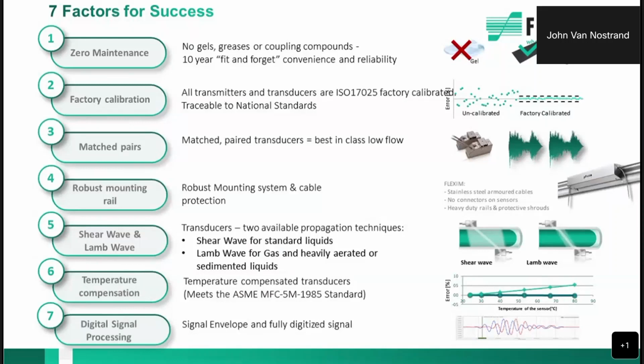We calibrate every pair of transducers that leave the factory. This means that you don't have to obtain zero flow or do a field calibration when you install. We match the transducers, the crystals inside the transducers, so that we ensure that we have a tight accuracy before we even send them to calibration, which we do on every pair of transducers and every meter that we ship. We calibrate that meter and transducer and you get a certificate.